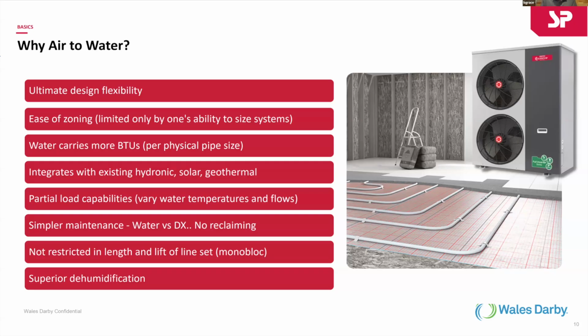Now, existing sounds like, hey, in some of your homes, a lot of you are doing the older homes in Manhattan, and around this area. They have cast iron radiators, and that's aesthetically pleasing to the house because of the age of the house. You don't want to lose that character of the heating. Well, lo and behold, you can use those radiators, and now in some ways they'll actually work better because we're running only 130, 140 degree water through them instead of 180 degrees. So they're not scorching hot. They'll actually make the house more comfortable because it's on all the time. So it's always warm, and it allows us to warm the room better.